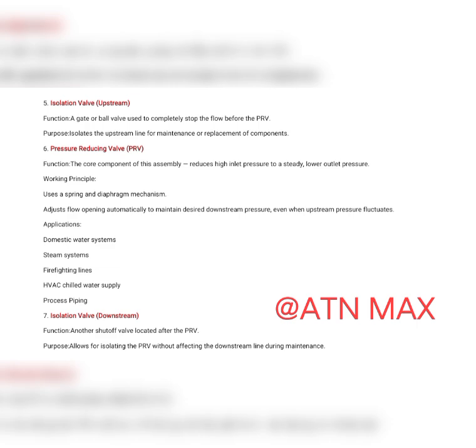Working principle: uses a spring and diaphragm mechanism. Adjusts flow opening automatically to maintain desired downstream pressure, even when upstream pressure fluctuates. Applications: domestic water systems, steam systems, firefighting lines, HVAC chilled water supply, process piping.